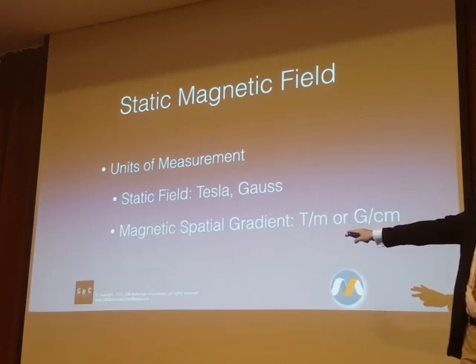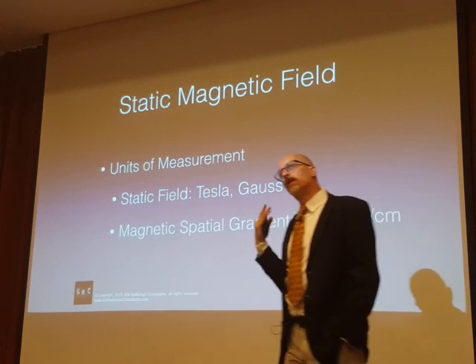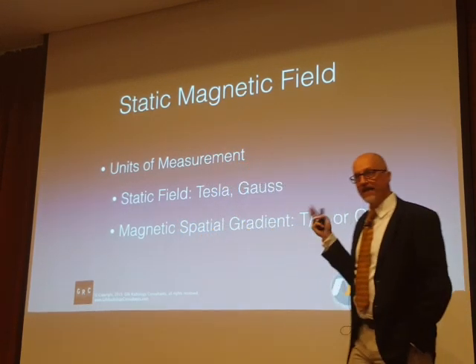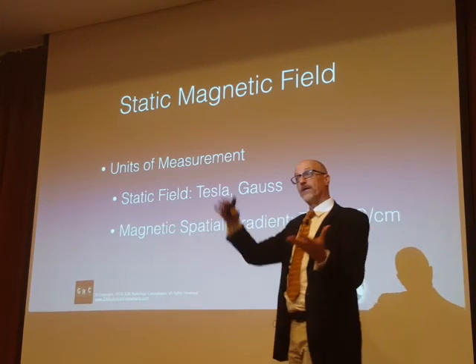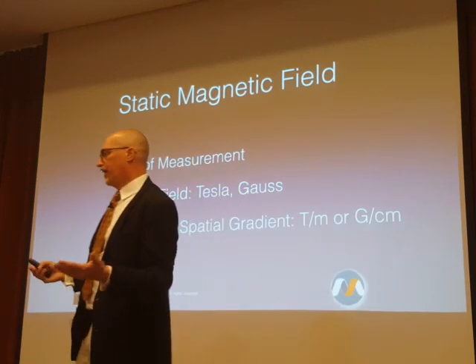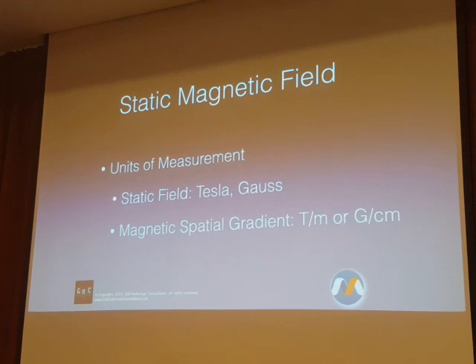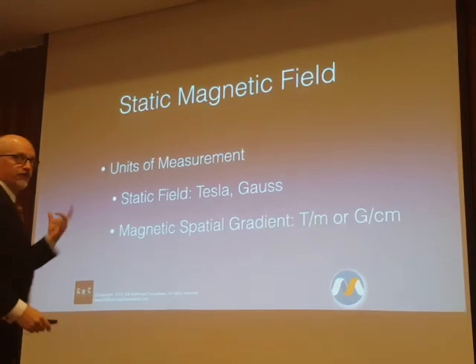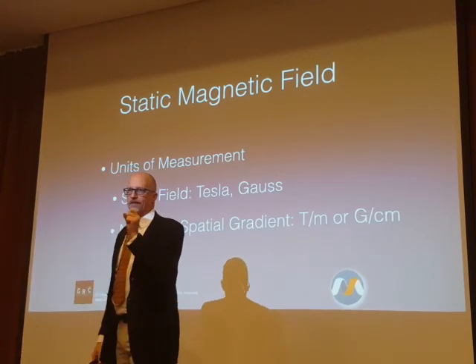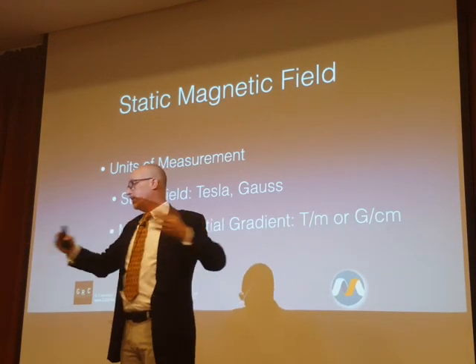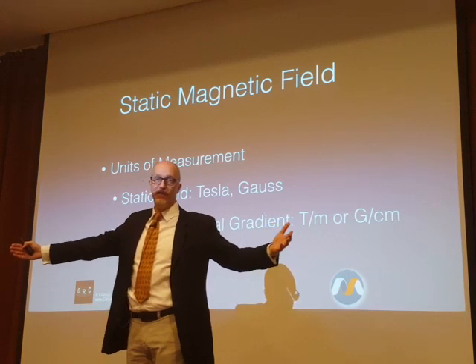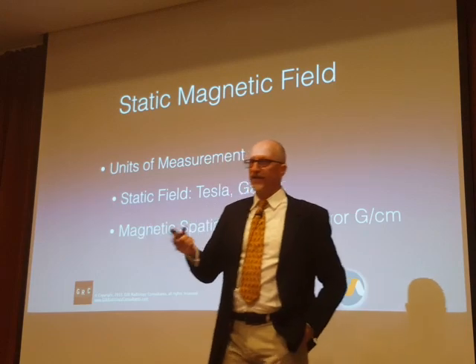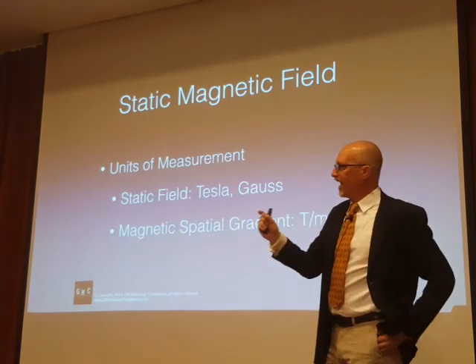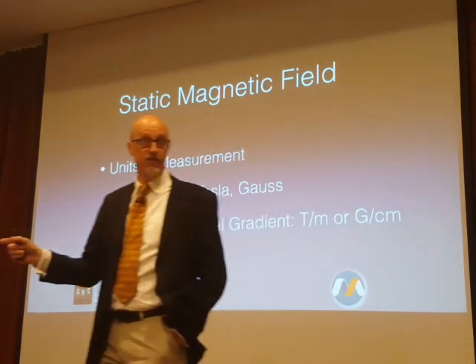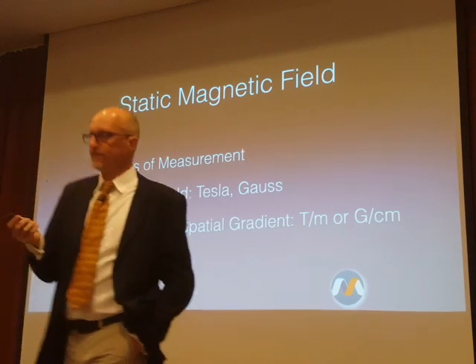We describe, in terms of the units of measurement, the static field in terms of Tesla or millitesla or Gauss. We define the magnetic spatial gradient in terms of the field strength change over some unit distance. The European standard for that is Tesla per meter. The US standard for that is Gauss per centimeter. Those values change over such small distances that I'm partial to Gauss per centimeter, because nobody in their right mind would ever measure a spatial gradient across a meter of space when we're talking about an implanted device that's 5 centimeters in size. Having it averaged over a meter just is not very helpful. Having it averaged over a unit of space that actually pertains to the implants and devices that we're looking at, in my opinion, is just a smarter way to do it.